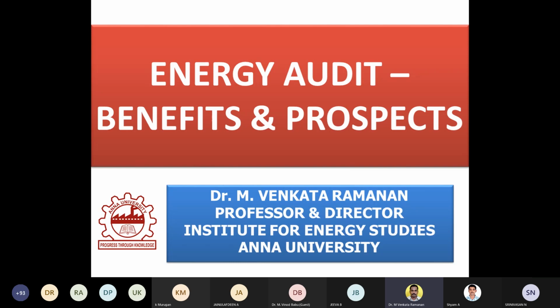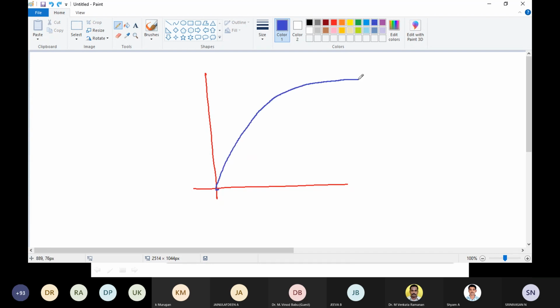There are different analyses on the motors itself, like motor efficiency. If you plot the graph, the efficiency of the motor will look approximately like this. At approximately 80% loading of the motor, the efficiency attains its peak, and it will remain almost stagnant up to about 95% loading. So this is the typical loading pattern at which the motor has to be loaded.